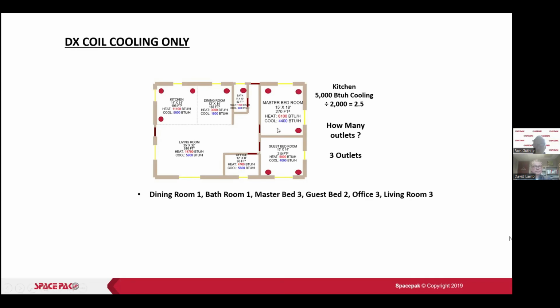For instance, here in the master bedroom, we have a heating load of 6,100 BTUs. We're getting 3,000 BTUs per full outlet in heat. So if you want to call the 100 BTUs close enough, that would be 2 fully open outlets there. In cooling, we've got 2,000 BTUs per outlet and a load of 4,400. So from a cooling perspective, you'd probably want to put 3 of them in that room.